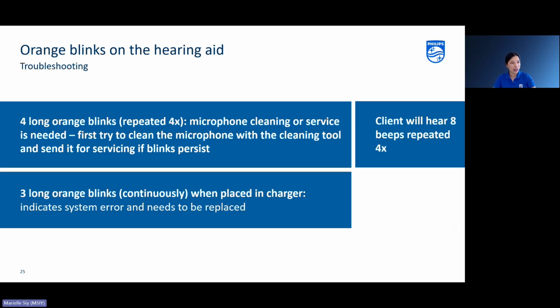I also got some questions regarding orange blinks on the hearing aid. Here is some information regarding troubleshooting. What if there are orange blinks? The first thing you need to check is the pattern of the orange blinks on the hearing aid. If it's 4 long orange blinks repeated 4 times, so 16 blinks altogether, then that means the microphone needs to be cleaned. You can try to clean the microphone yourself with a cleaning tool. If there's still a problem, then you can send it to the lab for servicing.